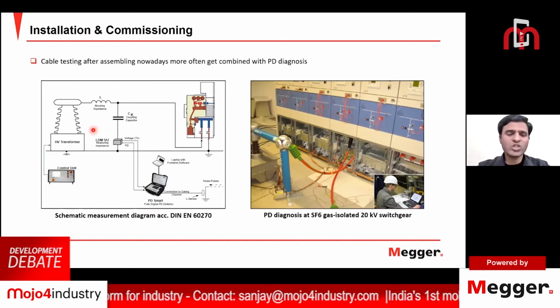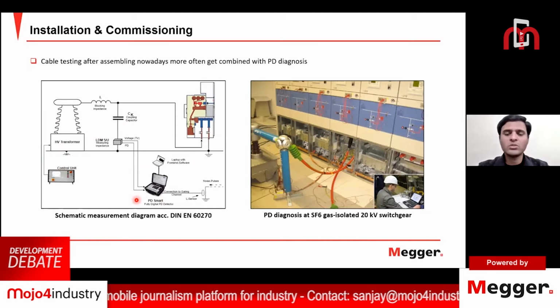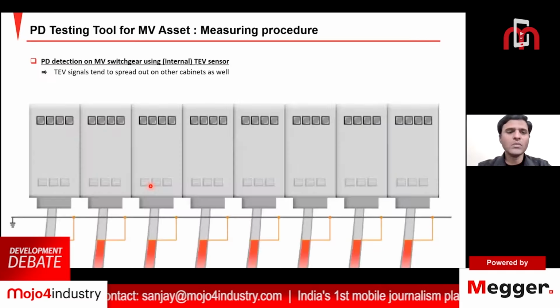This is the test method which is defined by IEC 60270. There should be a high voltage source. There should be a coupling capacitor between your DUT and a centralized device, which is used to analyze the readings and to identify whether there is PD and which type of PD is generated, by analyzing the PRPD pattern, which is the phase resolved partial discharge pattern.